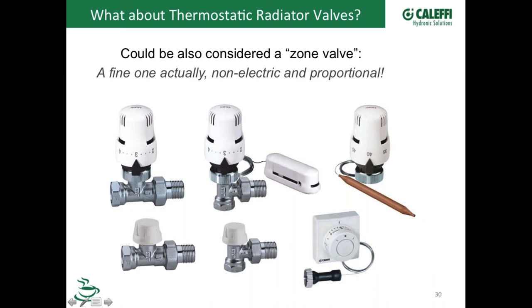If you wanted to sense maybe a baseboard down the road a little bit, you've got a little bit of a tube on here that can move the sensor remotely. We also have this one here that you could mount within a certain distance of the valve itself, and then this could be a wall-mounted thermostat. So you could still have a thermostatic valve and have control on the wall instead of having to bend over to the bottom of a radiator or something like that. We've got the remote sensors available for that.